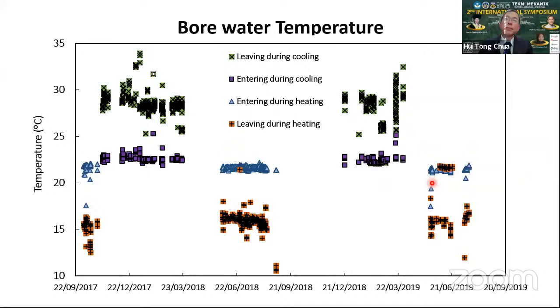Now, this is a very important graph tracking the temporal variation of the bore water temperature over time. You can see the monitoring started in September 2017 and ended in September 2019, over a span of 2 years. This is a summer period. There are 2 summer periods and we have 2 winter periods. This is the extracted groundwater temperature during the summer period, and there's a brief winter period here as well. You can see that they are holding pretty constant in terms of the baseline groundwater temperature. This is the returning groundwater temperature after cooling application.